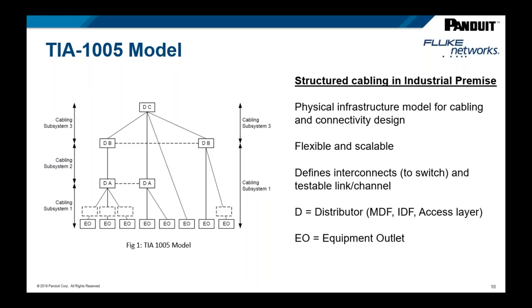The cabling subsystems start at the bottom and move towards the network core: the links connecting the equipment outlet form cabling subsystem 1, then subsystem 2 and subsystem 3 attach the network core. Within the distributors, patching interconnects or cross-connects occur, providing a testable and scalable plant floor cabling infrastructure. This model is quite flexible, allowing for variations in network topology and logical design.